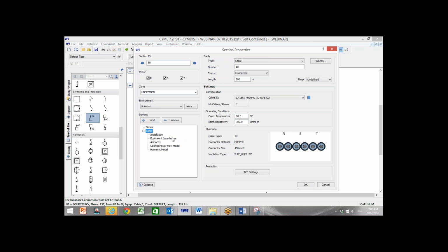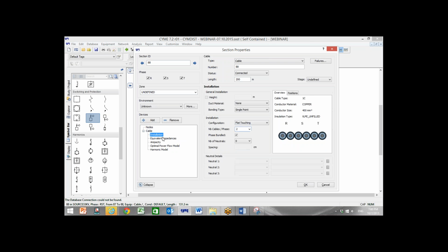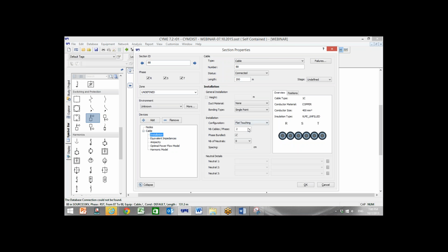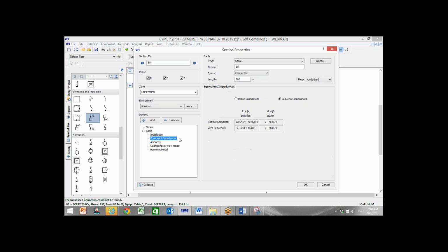You have to recalculate it, and CYME does this calculation. Okay, so now I have 3 cable, 3 cable per phase, and the impedance will be reduced up to 0.78. This does work if you have 3 run of cable per phase. The ampacity will increase, but the impedance will not.